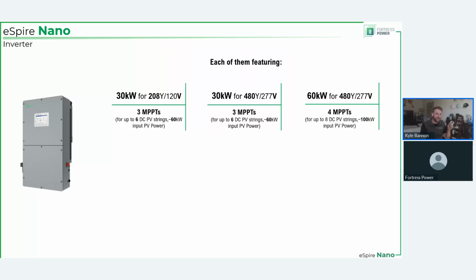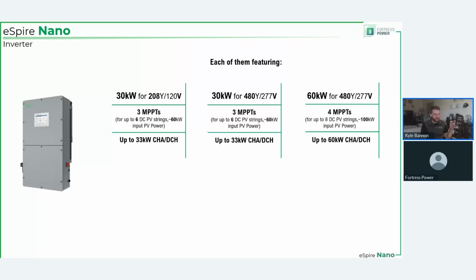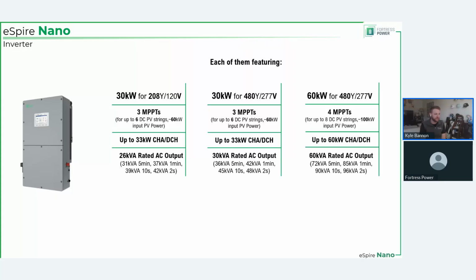Something to note: every string that gets plugged into the individual MPPTs here needs to be identical in terms of voltage, in terms of panels. Identical strings need to go into these MPPTs. But you can charge and discharge up to, for the 30K, up to 33 kW, just a little bit of overage there. For the 60K, it is capped at 60. We do have some rated AC outputs that can overload for very short amounts of time. That overload protection is nice, especially when you're talking about backed up loads and things with inrush current. So depending on which model you get and what voltage is selected, we'll have different rated AC outputs for different amounts of time over that as well.